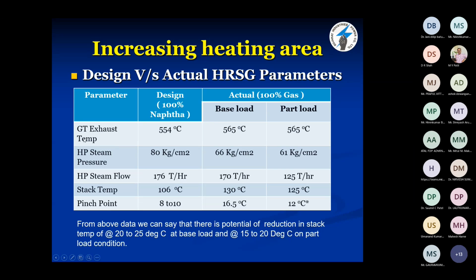So at base load, the GT exhaust temperature was designed at 554 degrees centigrade. At base load, it comes to 565 degrees centigrade with 100% gas. And at part load operation also, it is 565 degrees centigrade only. The steam pressure was designed for 80 kg, but due to 100% gas, the steam pressure was 66 kg, and at part load it was 61 kg. Steam flow was designed for 176 ton per hour, and now with gas at full load it is 170 and 125 at part load. The main thing is the stack temperature.